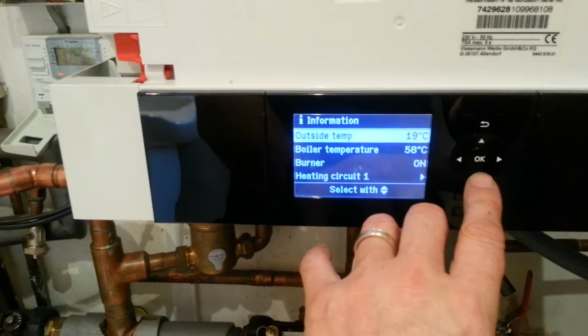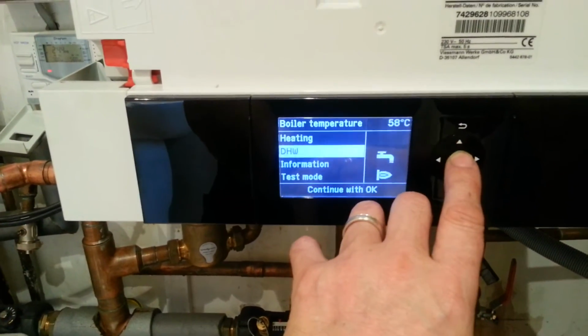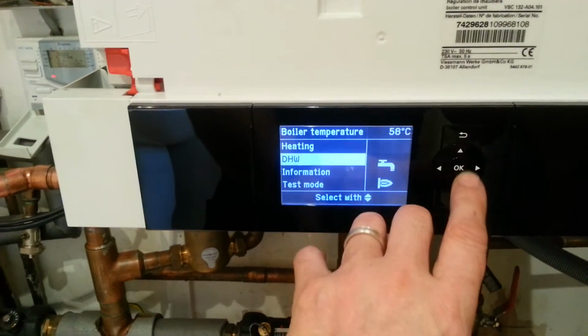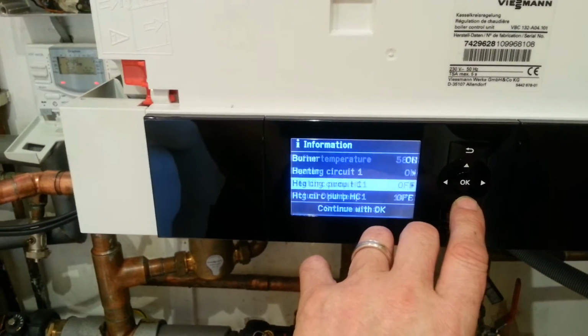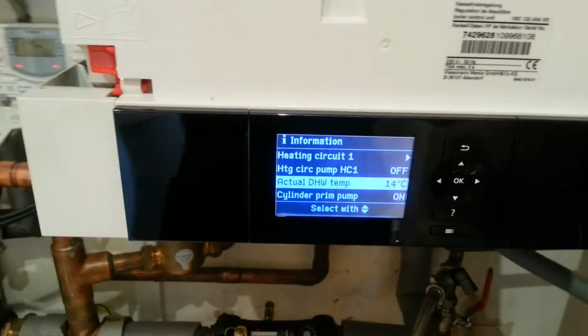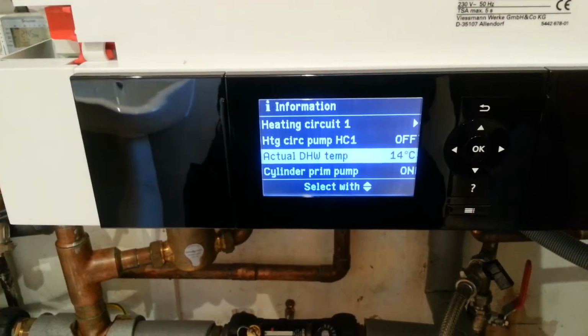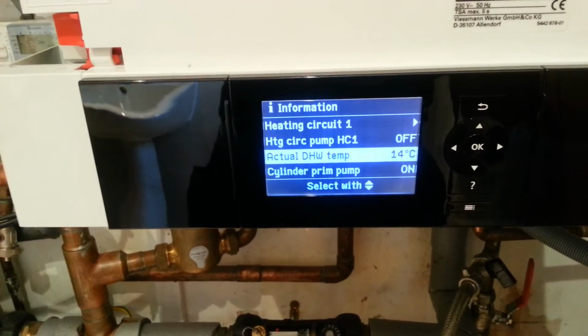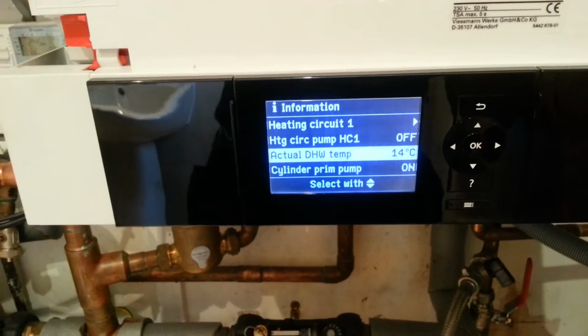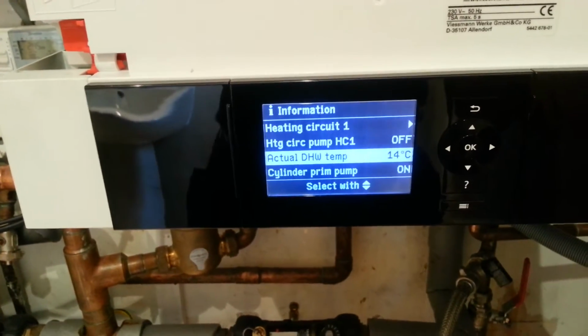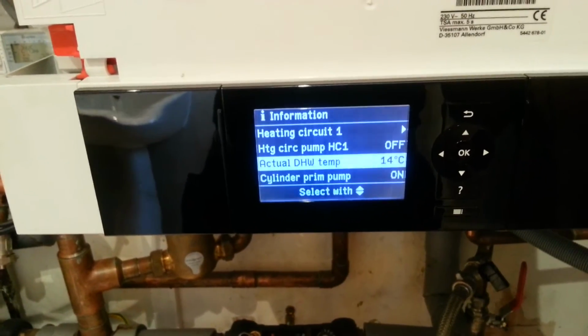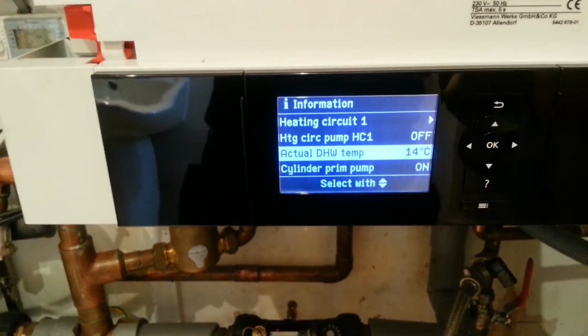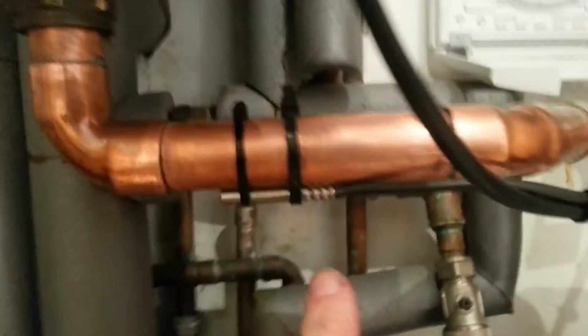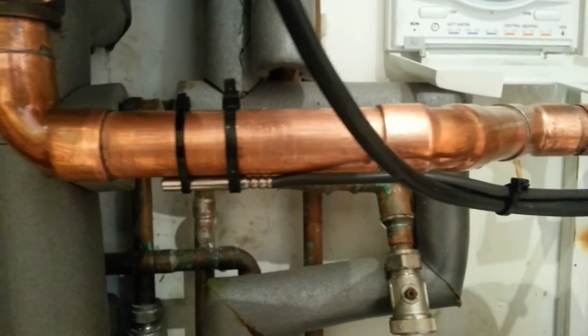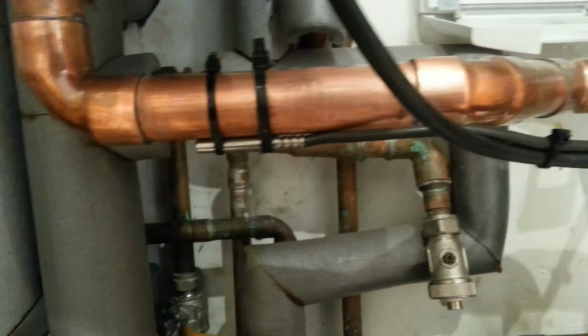So if I have a little look at the, see if I can find it, domestic hot water, set to 55, information, actual domestic hot water. So the boiler thinks the water's 14 degrees. Once that's satisfied, it'll see 75. It'll never see any difference, either 14 or 75, which as far as the boiler is concerned is on or off. Whereas if it's plumbed in with a Viessmann cylinder using a cylinder sensor, which looks like the header sensor that I've applied here, it would actually see the true temperature of the water in the cylinder.